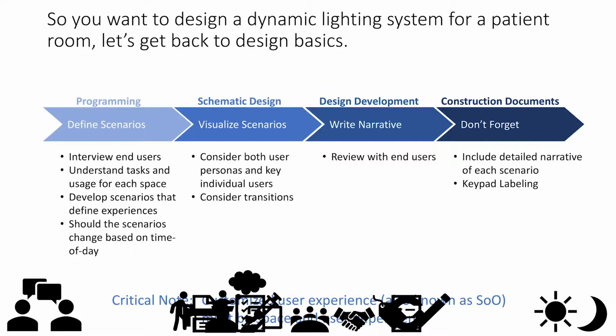And then, you write your narrative up, which we know as a sequence of operation, and review it with the user. I interviewed you guys. This is what I think we discussed. Is this correct? Is there anything we need to change? And then, don't forget on the construction documents, we need that detailed narrative of each scenario. And we also need to know what the keypads are going to do.